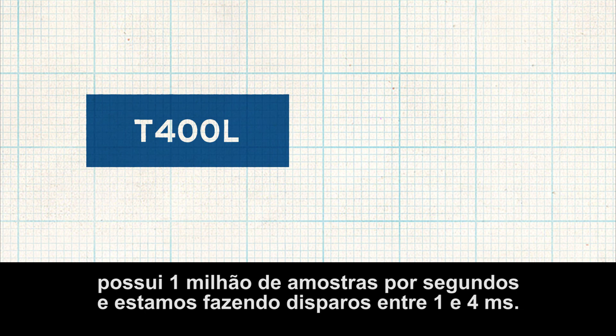So why is this important? Well, with the time domain processing that we're releasing in the T400L, we're sampling at 1 million samples per second, and we're tripping in 1 to 4 milliseconds. Our TiDL technology now samples at 24 kilohertz, but it's going to go to a megahertz. That's the future. That's where we're going, and that's why the TiDL solution has a much better future than the 9-2 standard.